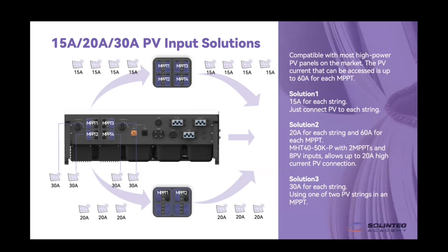And if we want to connect with some even higher current PV panels, we can use this solution. That is to say, using the normal version of our inverter with 4 MPPTs, and just using one PV input per MPPT to connect our PV strings. In this case, the maximum PV input current is 30 ampere. That is why we can offer our users different solutions according to the different requirements of their project.